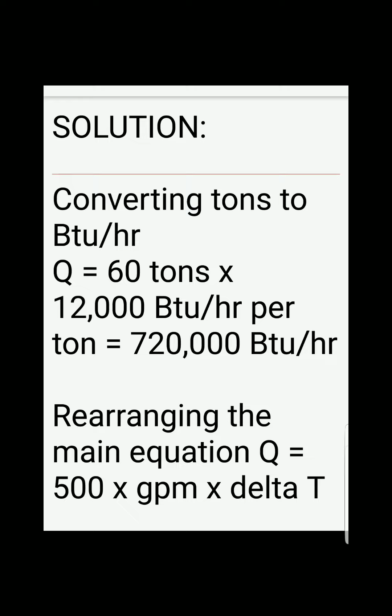And we need to rearrange the main equation of cooling capacity. Q equals 500 times GPM times delta T in order to come up with the delta T being Q divided by quantity 500 times GPM.